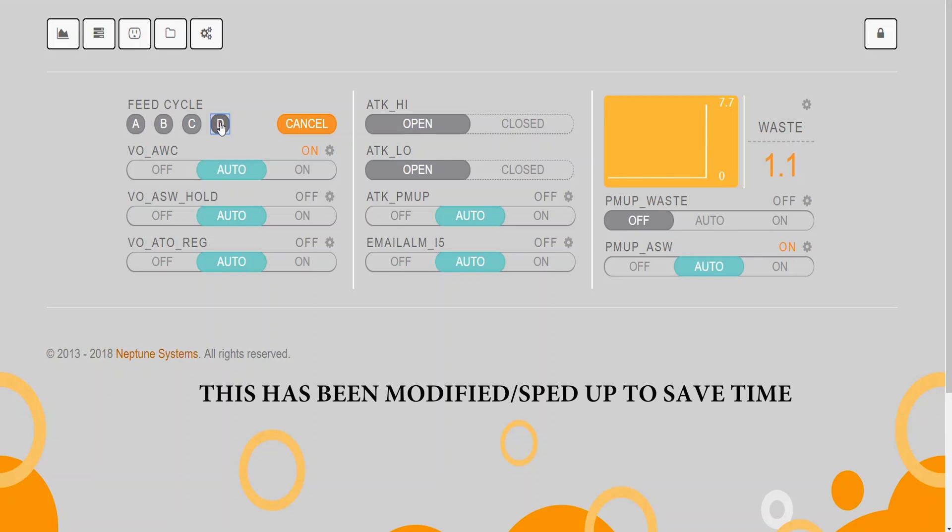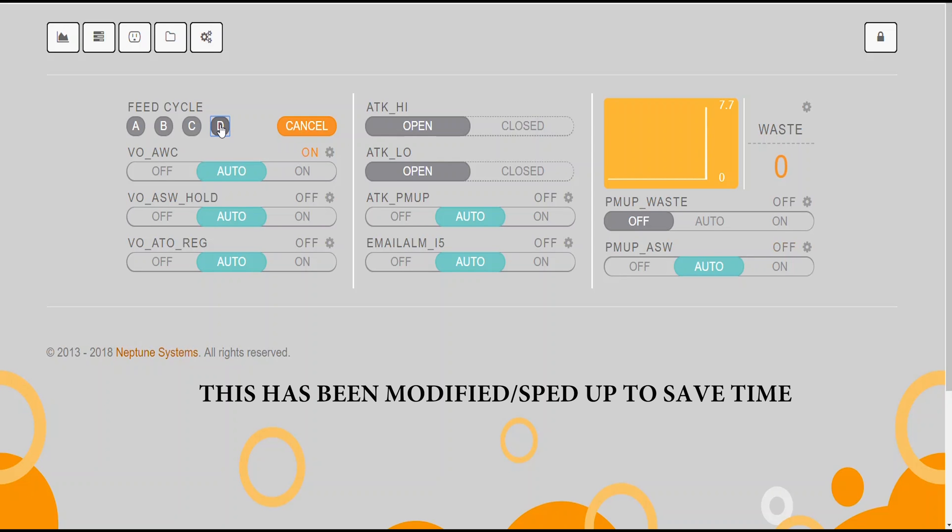Now, once that happens, VO_ASW_hold goes off. This is now going to allow water to be pumped from my water reservoir into my system, into my sump. So PMUP_ASW turns on and that continues to pump water until it reaches the optical float switch on my ATK. That is the trigger that will tell it stop pumping saltwater into the system. Now, once that turns off, the saltwater water change is complete. Now, if it pumps too long, I think it was 80 minutes, then the system will tell that saltwater pump to turn off and it will send me an alert knowing that something may have gone wrong. It doesn't necessarily mean something's gone wrong. It just means it pumped for a longer time than I expected to.